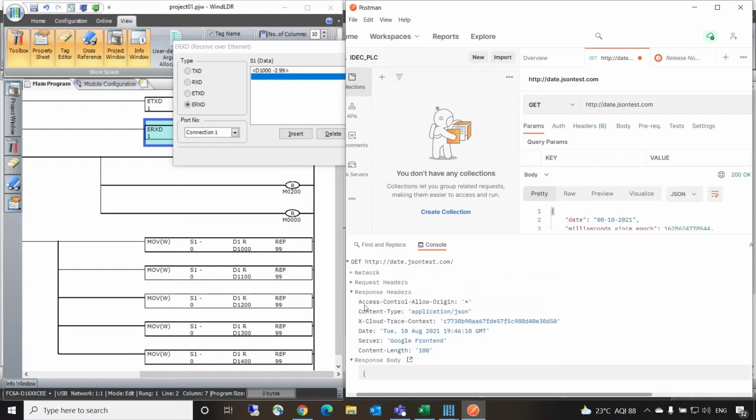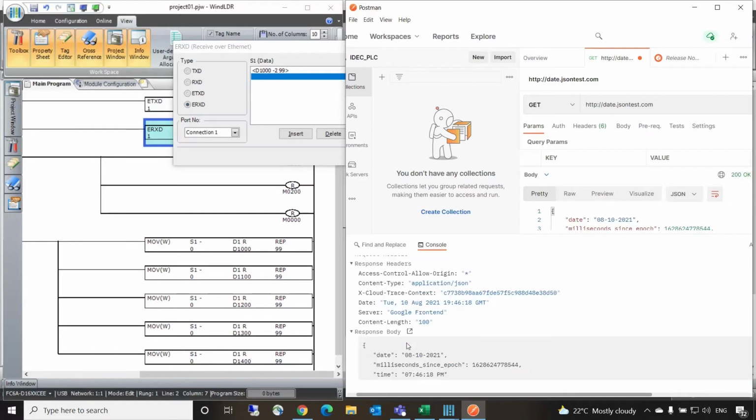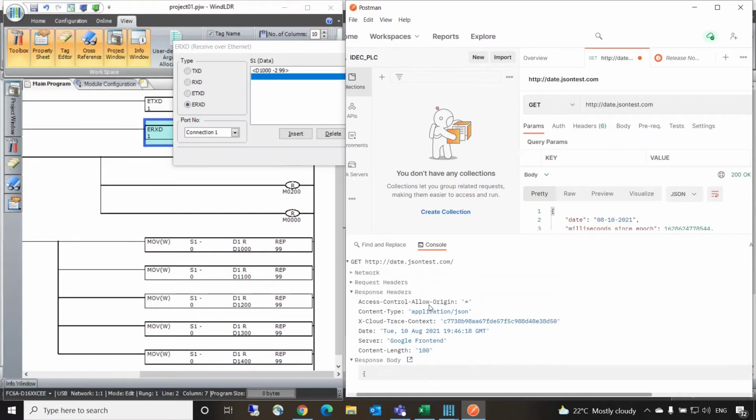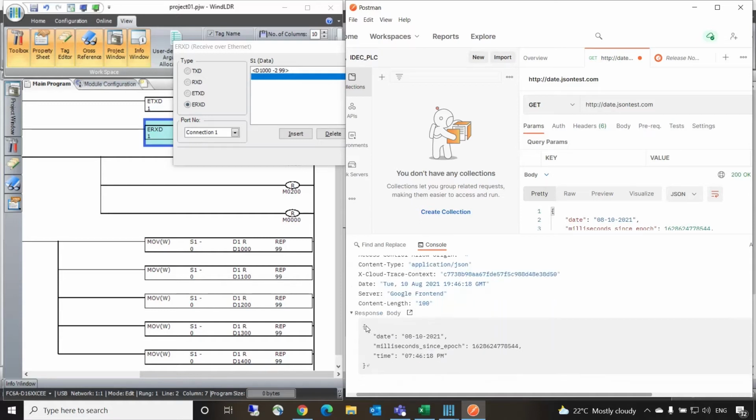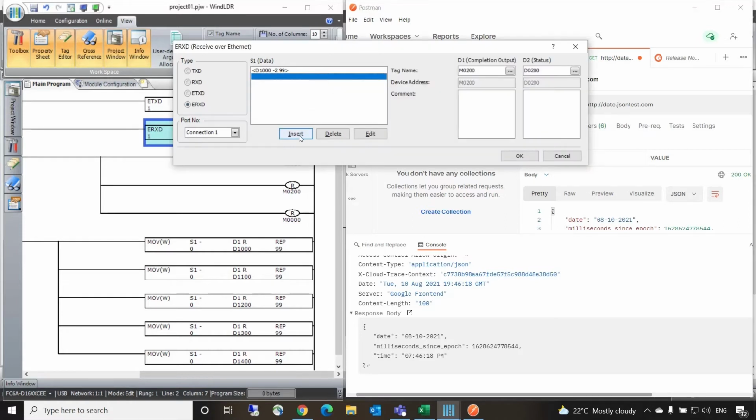So we have to calculate each and every ASCII character we have received in the response. Once you calculate the ASCII letters, like A, C is one register. So just calculate everything from A, C till 100, the apostrophe, and again the curly braces, from here to the last here. So this complete data we will be receiving in the PLC. So for that, how many registers are required, that we need to mention. So I'll take additional registers here anyhow.